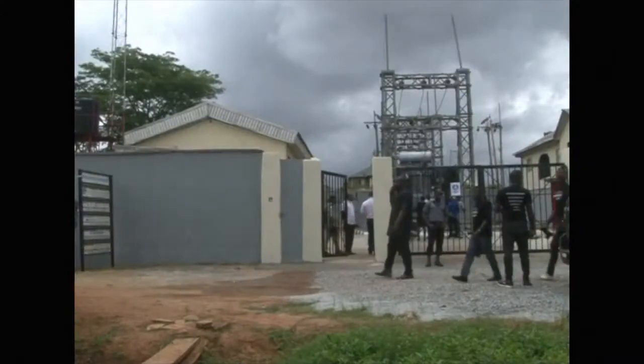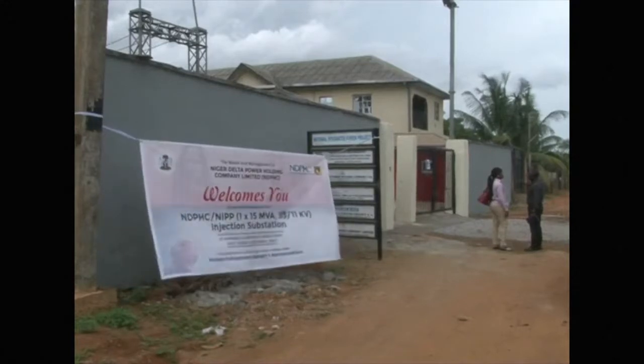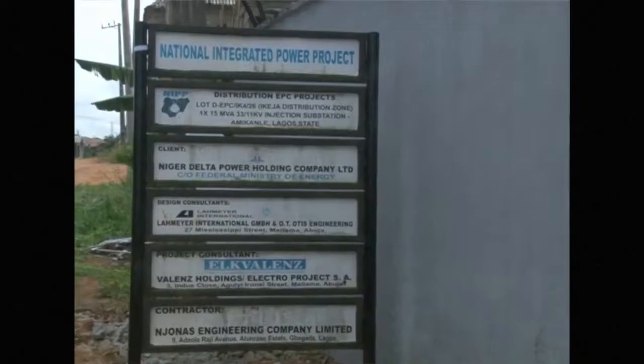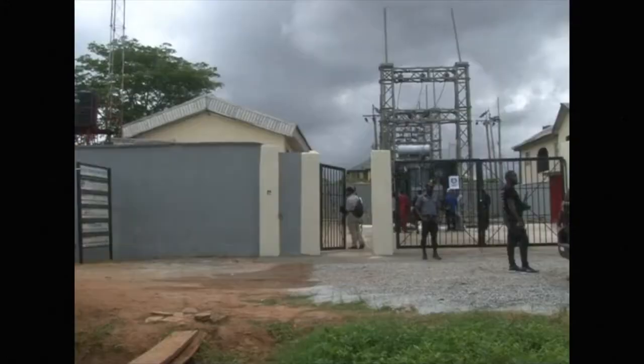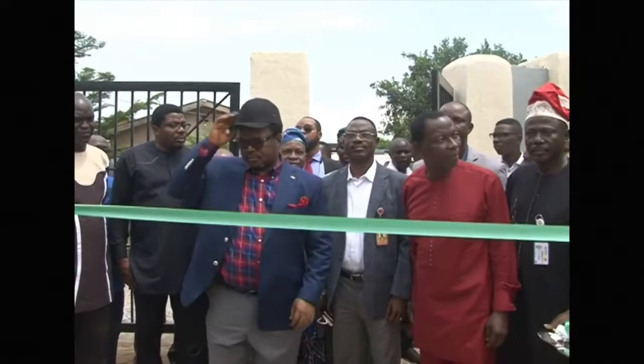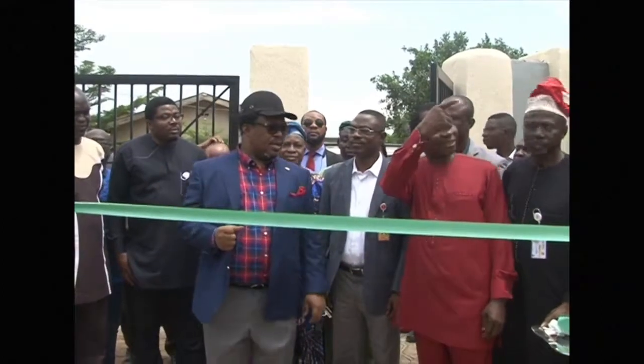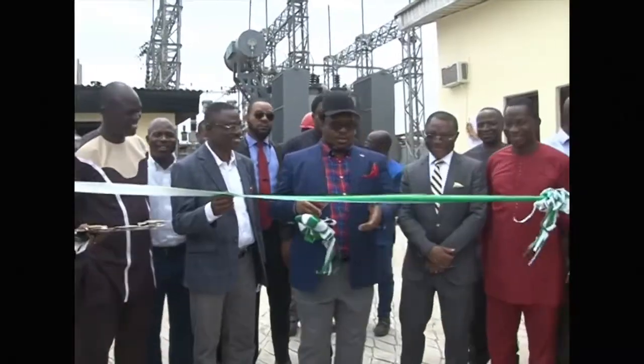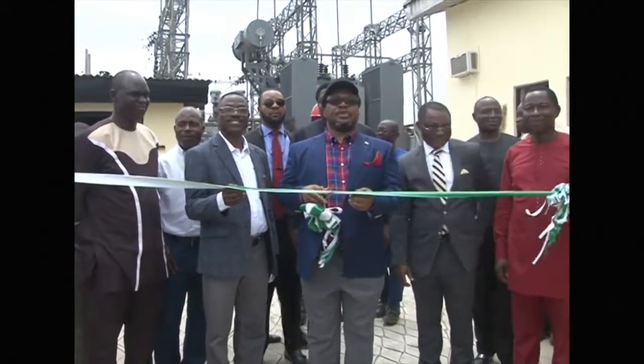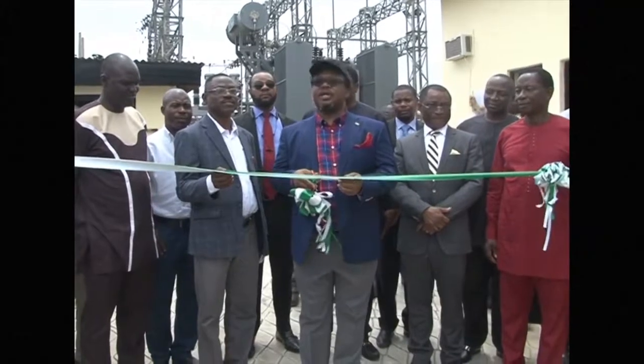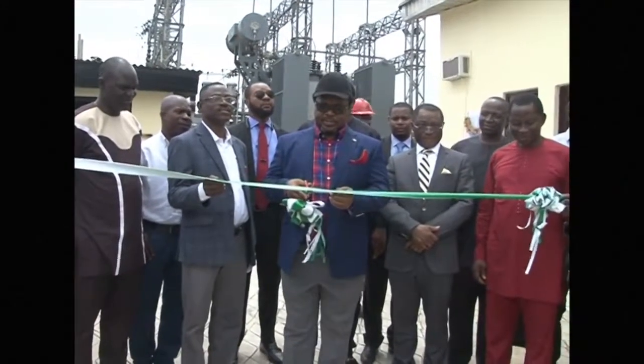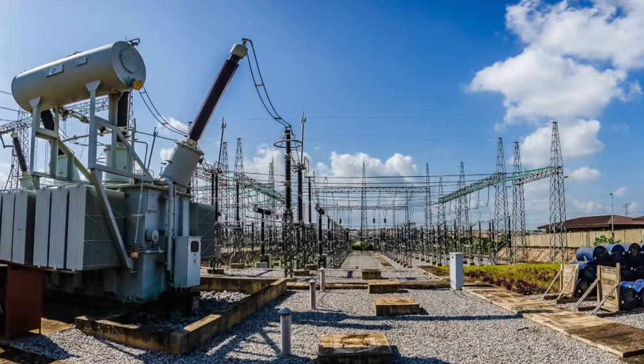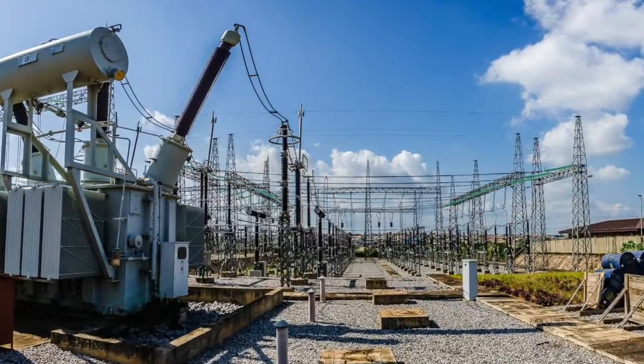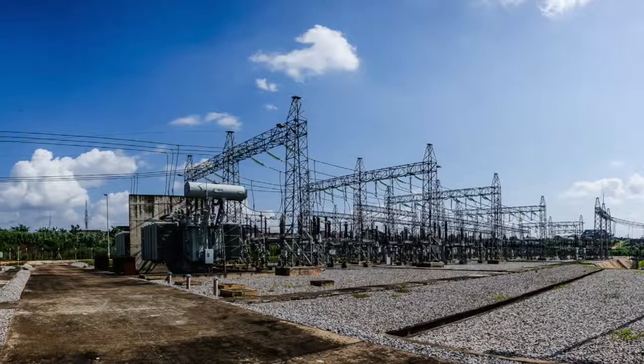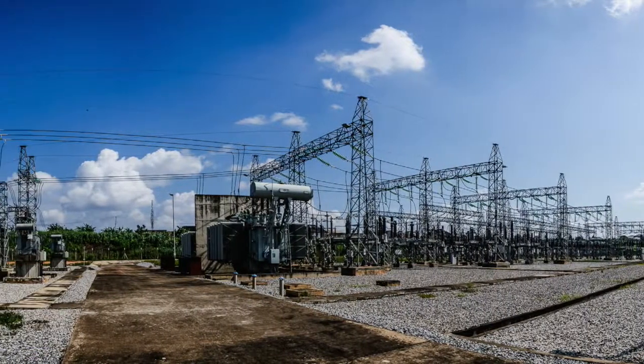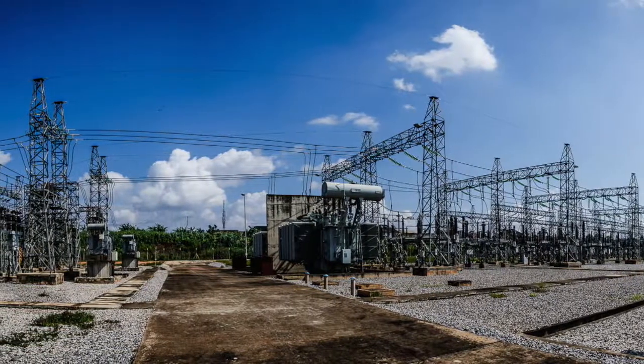Recently, the NDPHC commissioned two 15 MVA 33/11 kV injection substations in Amikonle and Abule Taylor areas of Alimosho local government area of Lagos, as part of efforts to boost power supply in the commercial hub of the nation. The Amikonle and Abule Taylor injection substations take supply from the Ayobo transmission station through a dedicated 22.5 kilometer 33 kV feeder and 48 kilometers of 33 kV feeder respectively.